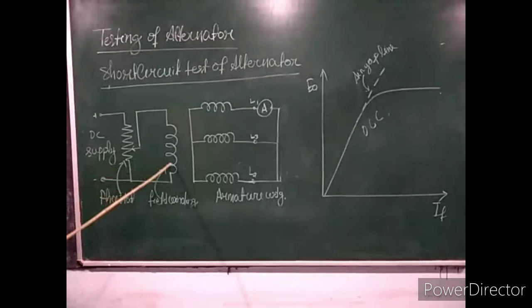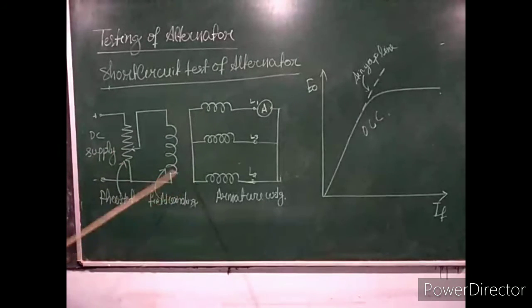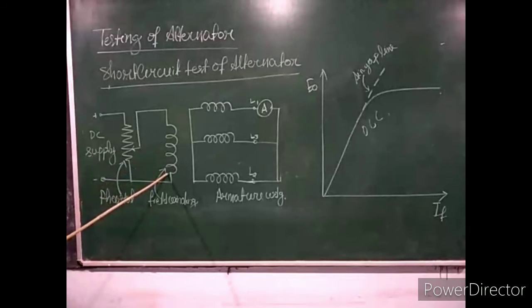The field is excited by giving a DC supply. Here you excite the field or raise the value of its current by varying this rheostat from 0 to 150 to 200% of full load current. And here you also connect one ammeter.